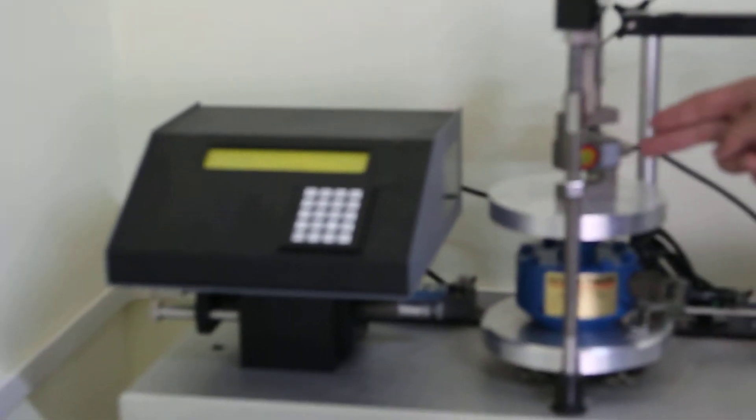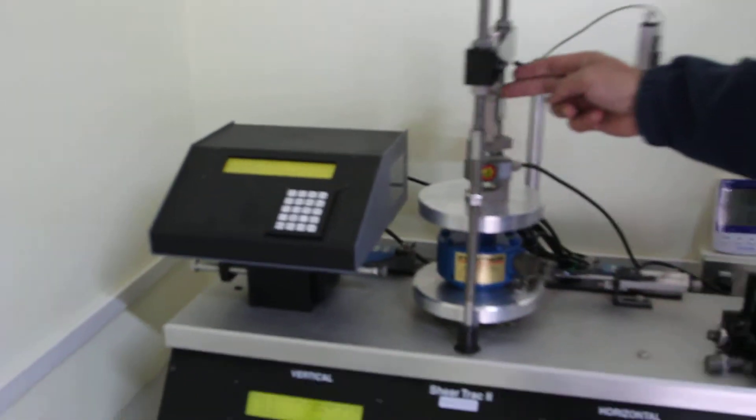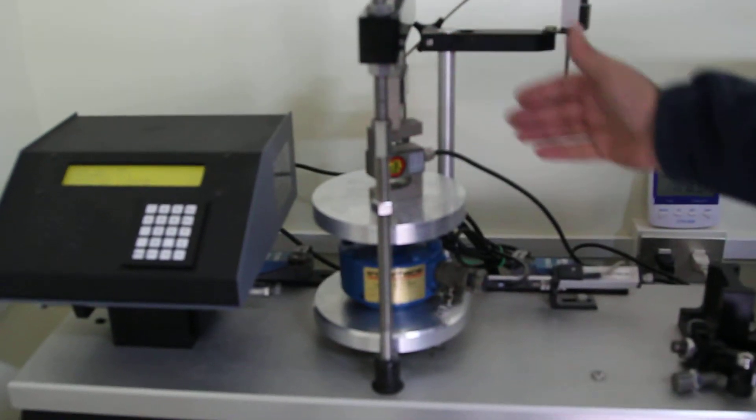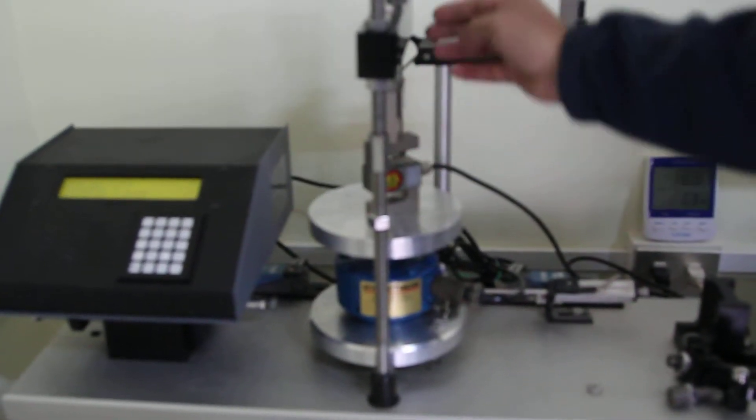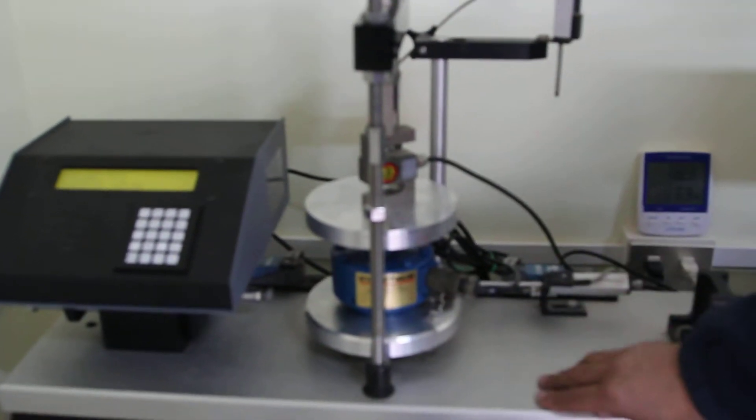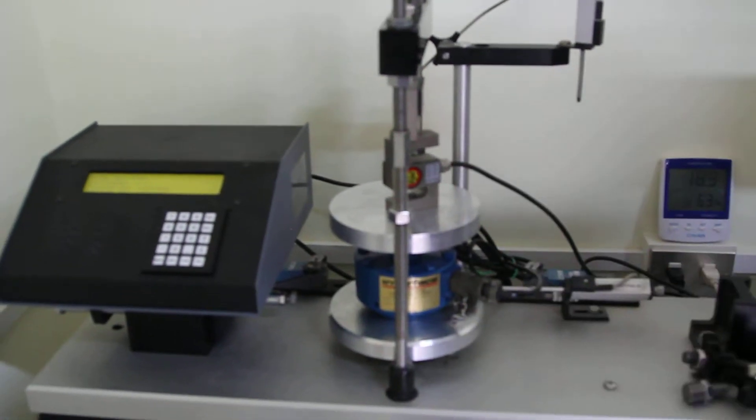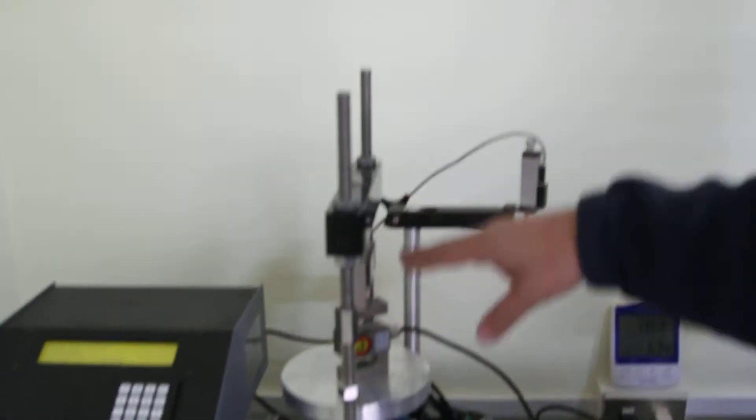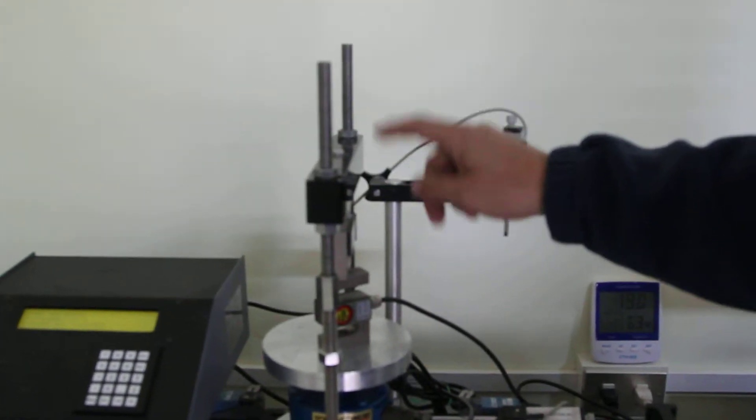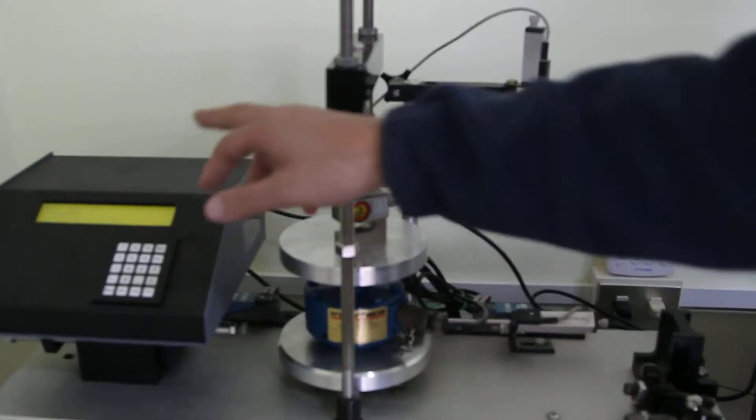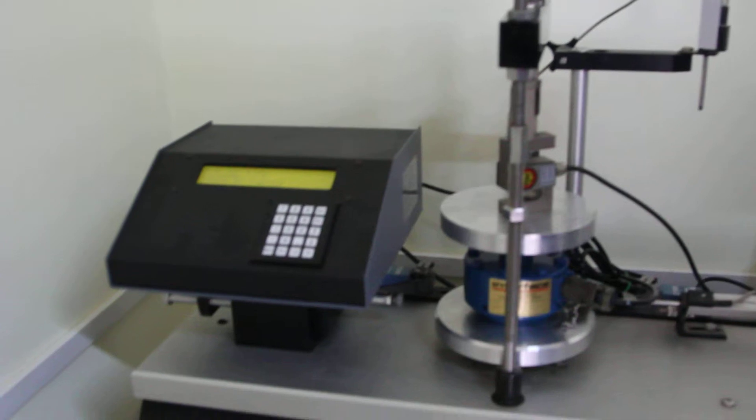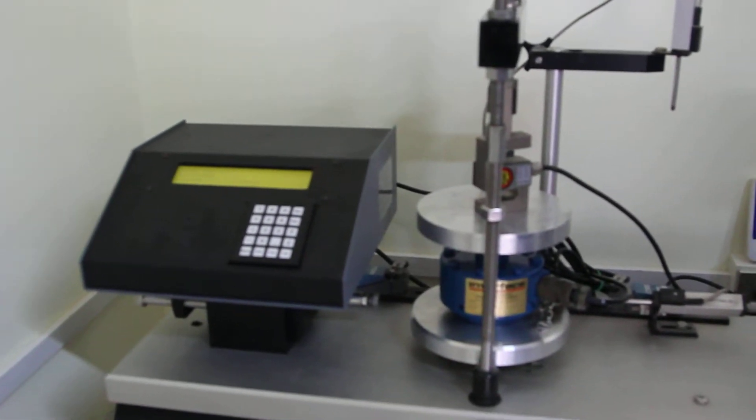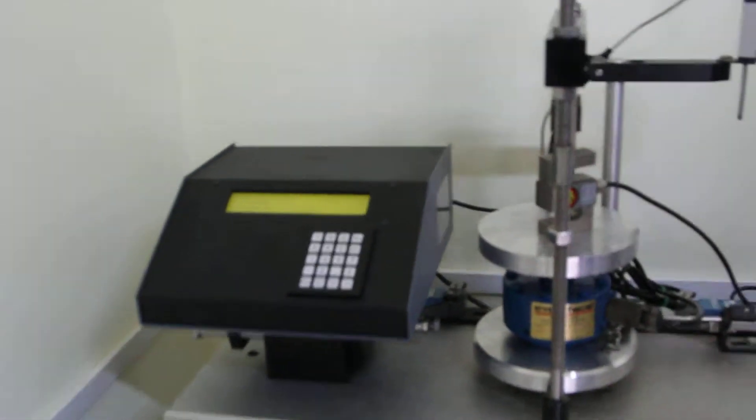We are doing a double calibration of the two, the vertical and the horizontal. We mounted them with some extension rods. We removed the water bath. And what we are going to do is we're going to apply the vertical load and we're going to read both the vertical and horizontal against the calibration reference. So we are going to be using the shear software.